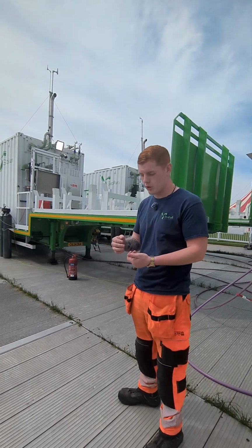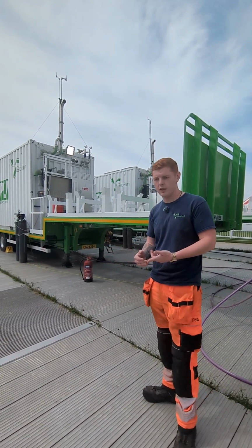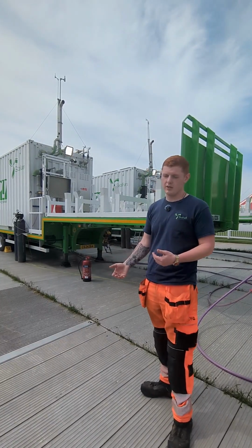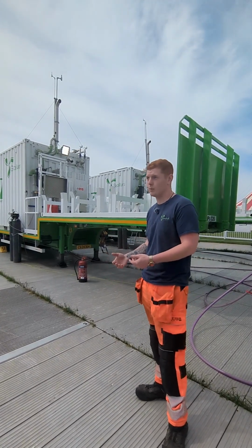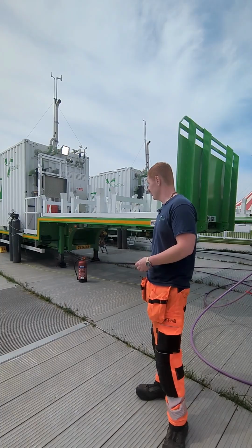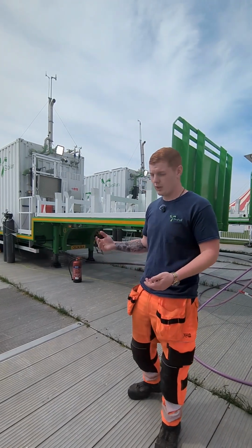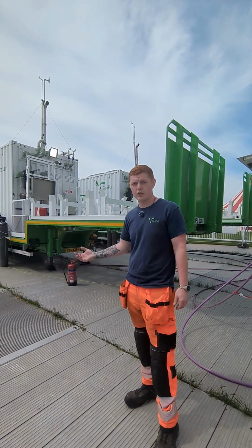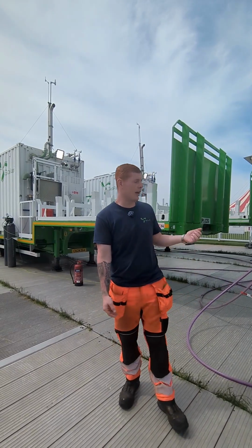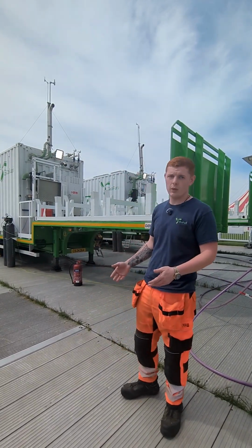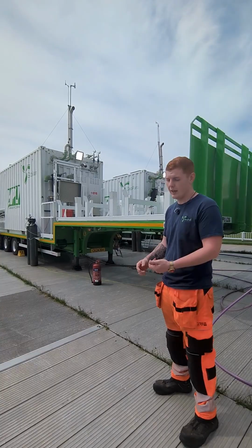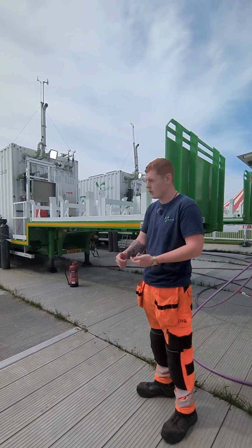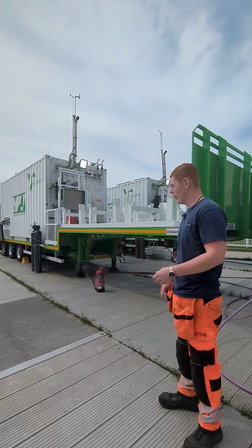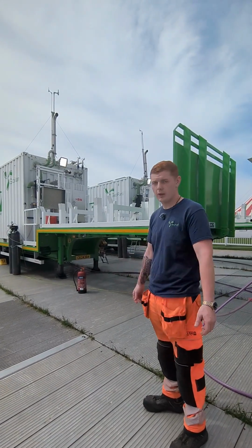We use 2 UPS systems in each unit, which provide instantaneous power for any load spikes or load drops. The fuel cell recharges the batteries. If we were to lose a fuel cell, or for some reason ran out of gas, you've got that 250 kilowatt hour of battery storage to either get an engineer here for a fix, or to swap the gas out, or just get the fuel cell back up and running.